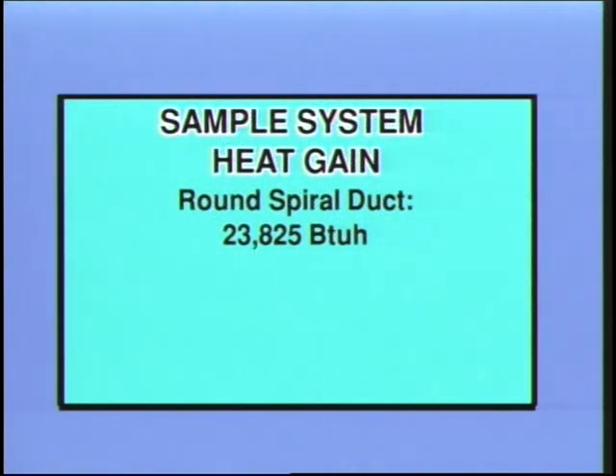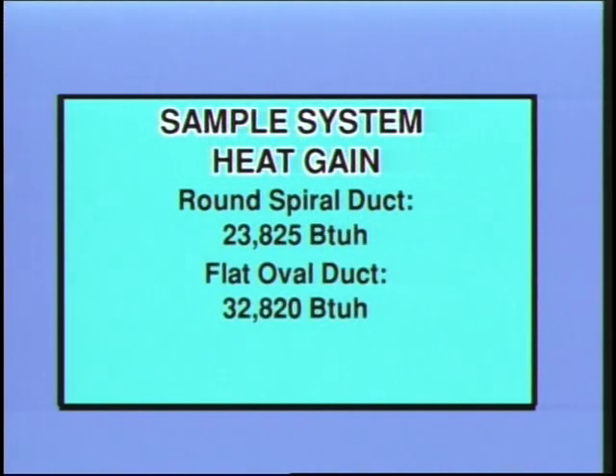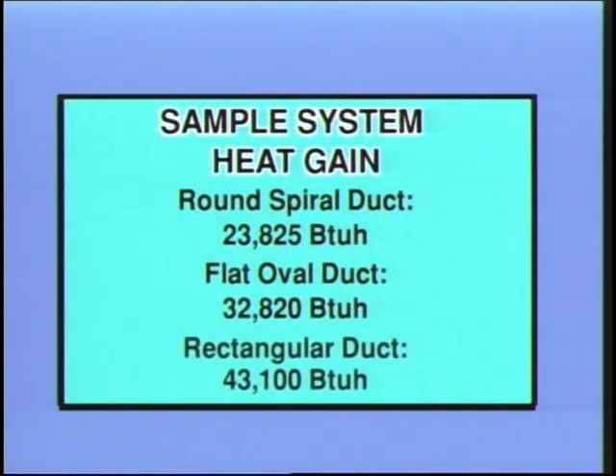Part of the heat gain came from a 90-foot section of round spiral ductwork wrapped with 2-inch fiberglass insulation, conveying 55-degree air through a 115-degree attic. The 32-inch diameter round spiral duct had a calculated heat gain of 23,825 BTU per hour. The 60-inch by 16-inch flat oval duct heat gain with the same 2-inch insulation was calculated at 32,820 BTU per hour.